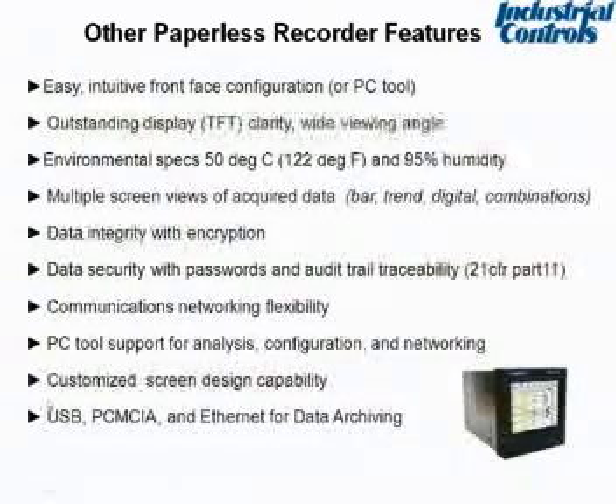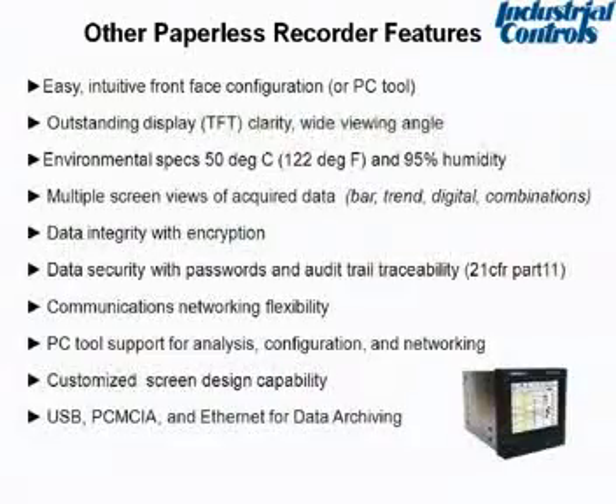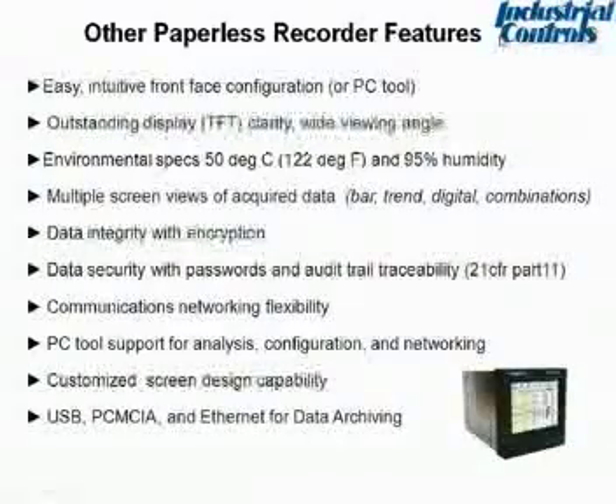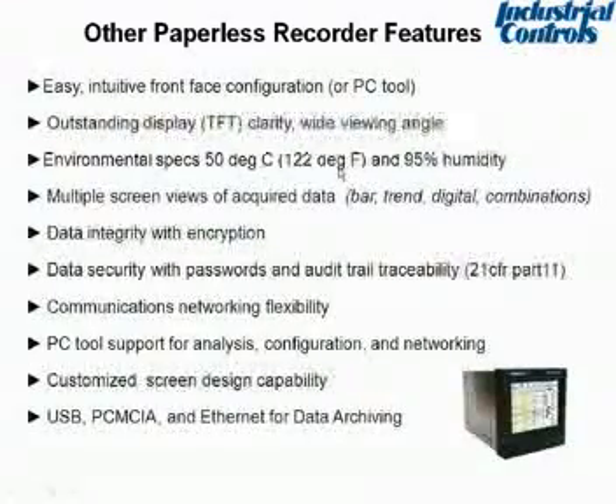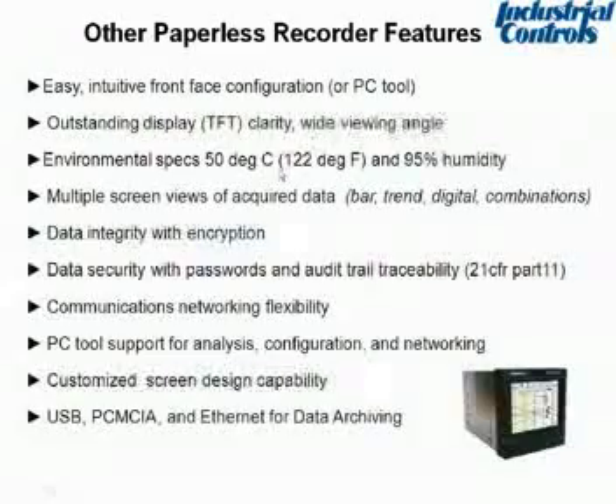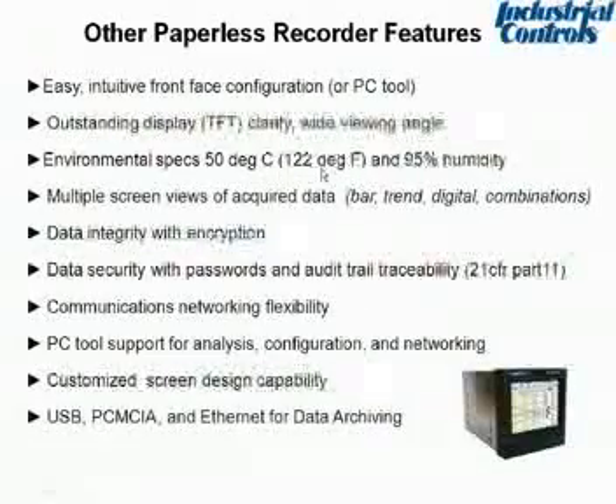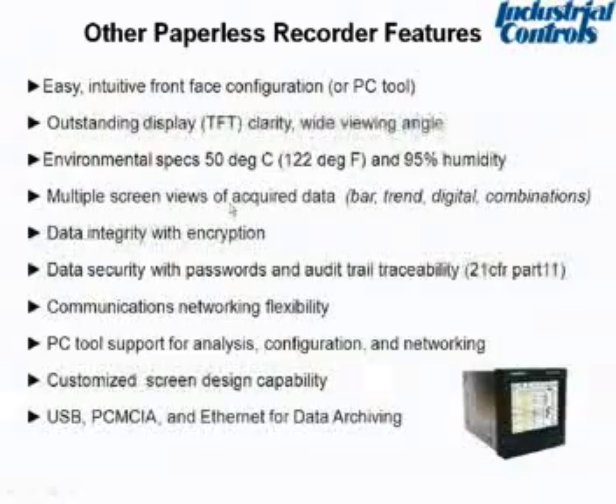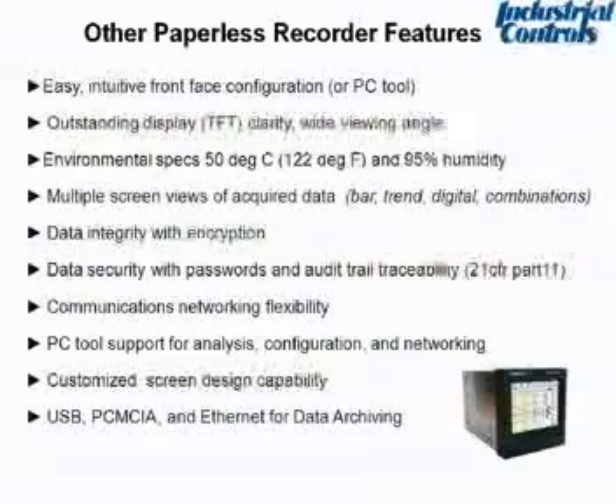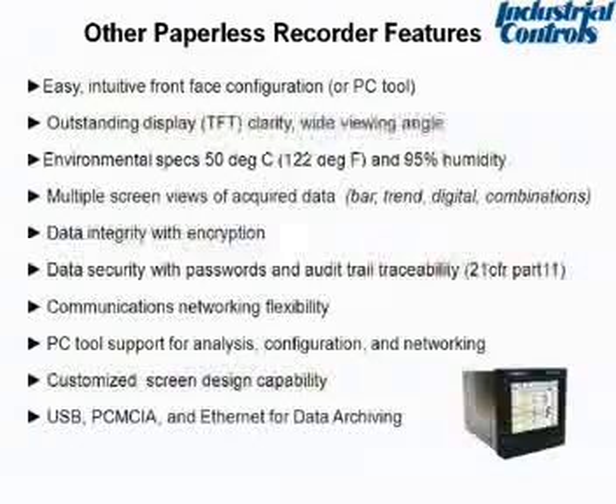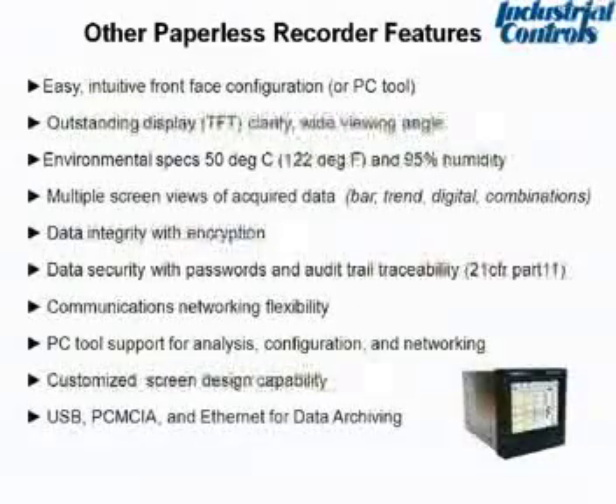The TFT technology is the same technology used in GPS systems in automobiles, giving you a nice wide viewing angle. The environmental specs on the paperless recorder are now as good as the paper recorder, up to 50 degrees C and 95% humidity. You also get multiple screen views of the data, whereas with the paper recorder you're pretty well dedicated to the type of chart you have—horizontal, vertical, or circular.